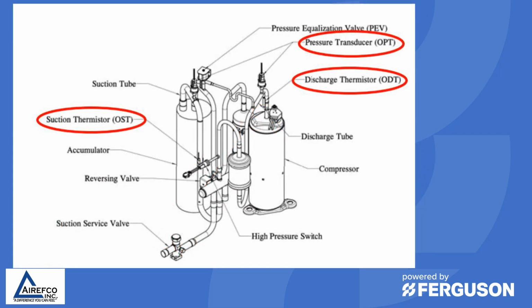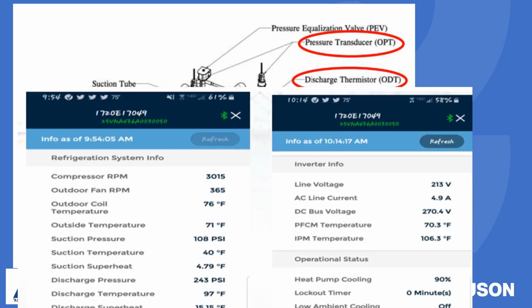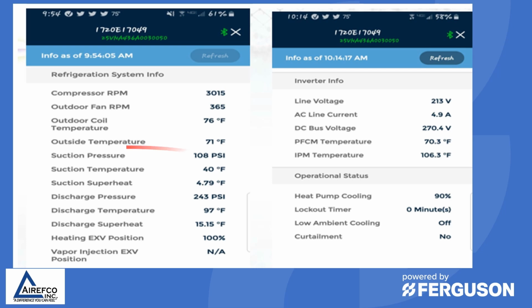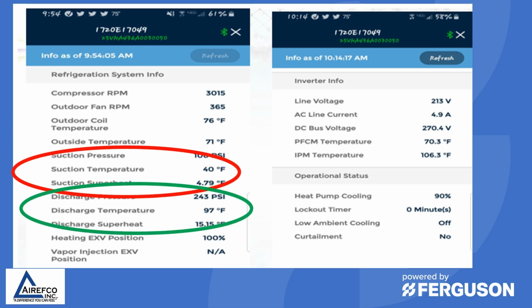So with these pressure transducers, the high side and the low side, and with a suction thermistor and a discharge thermistor, we are taking pressure and temperature. And what does that translate to? It translates to suction superheat and discharge superheat. So without even putting a set of gauges on these units, we can now, by remote access, check the charge and the operating temperatures and pressures of the system without even getting into the system itself.